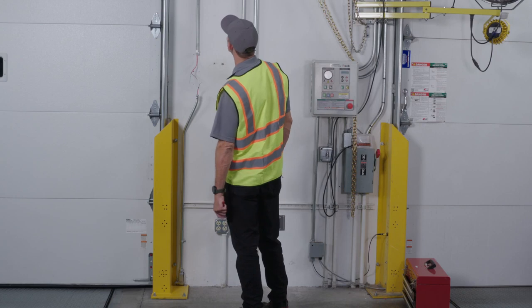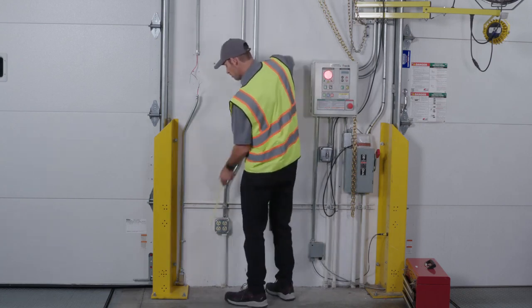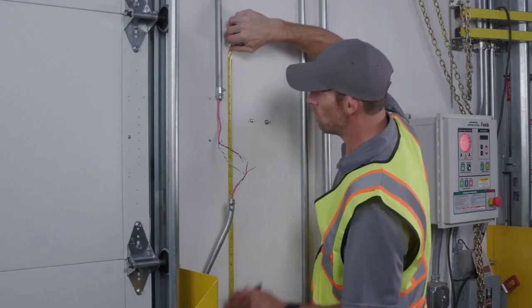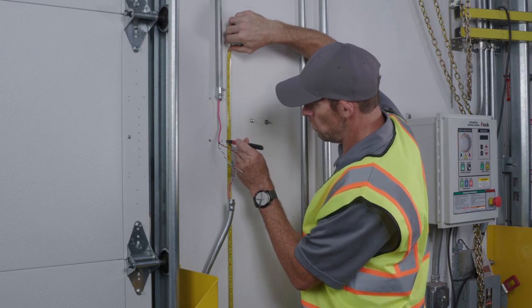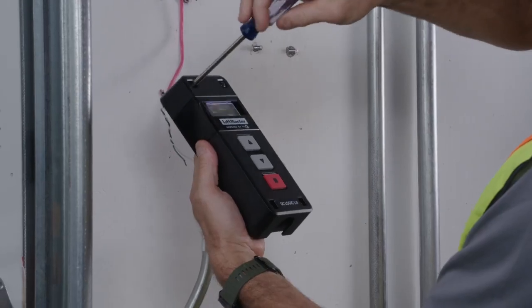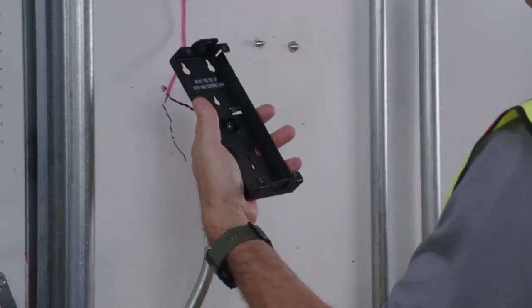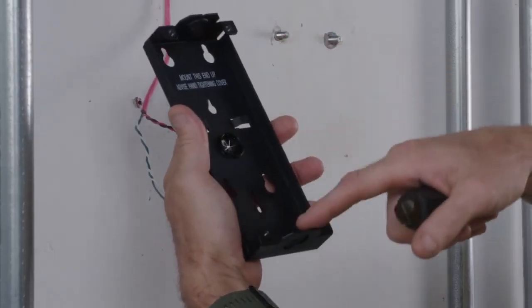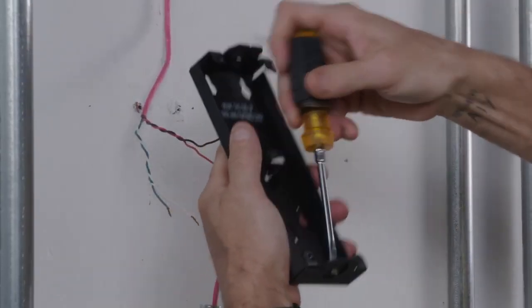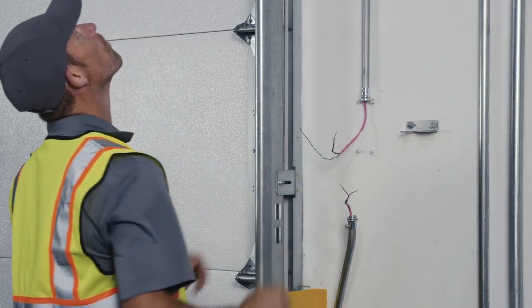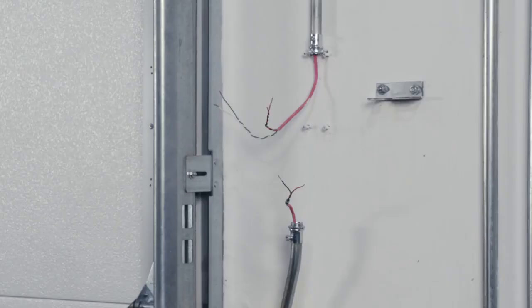Follow these steps to mount the wall controller. Measure and mark the wall at the appropriate height per regulatory requirements. Loosen the screws to remove the cover. Remove the knockouts from the mounting bracket. You will need to supply wire for the wall controller. Use 2 conductor wire that is 14 to 22 gauge stranded or 12 to 22 gauge solid wire.